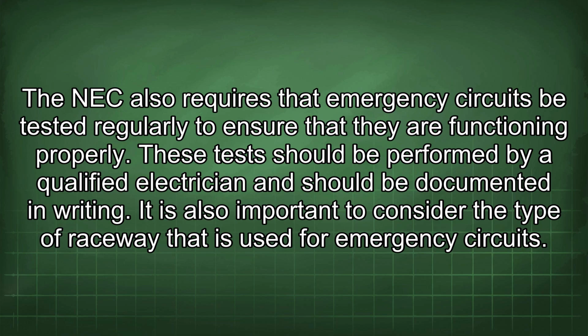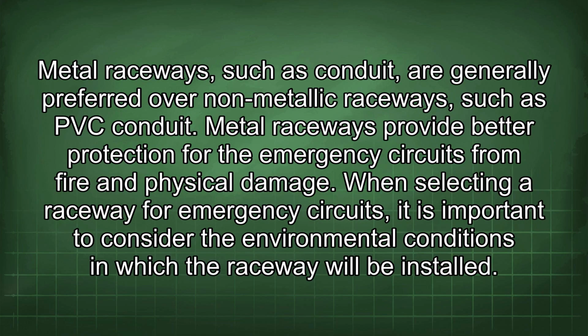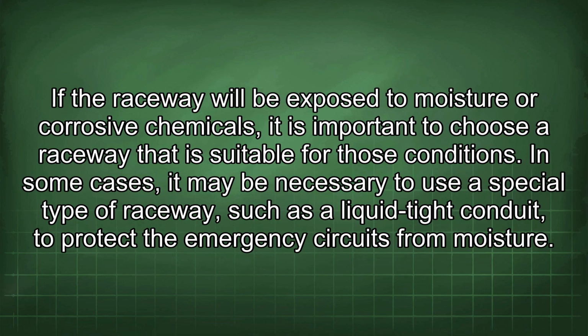It is also important to consider the type of raceway that is used for emergency circuits. Metal raceways, such as conduit, are generally preferred over non-metallic raceways, such as PVC conduit. Metal raceways provide better protection for the emergency circuits from fire and physical damage. When selecting a raceway for emergency circuits, it is important to consider the environmental conditions in which the raceway will be installed. If the raceway will be exposed to moisture or corrosive chemicals, it is important to choose a raceway that is suitable for those conditions.